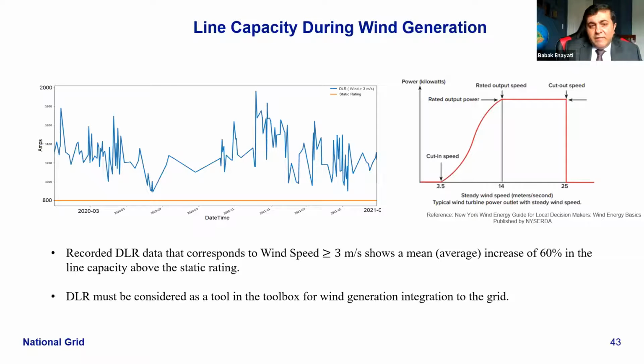With the data from our transmission line, I looked at any rating above the line where we have 3 meter per second wind speed. The blue line shows DLR for wind speed 3 meter per second and above, and this shows a 60% increase in line capacity. That is huge, it's a big number.